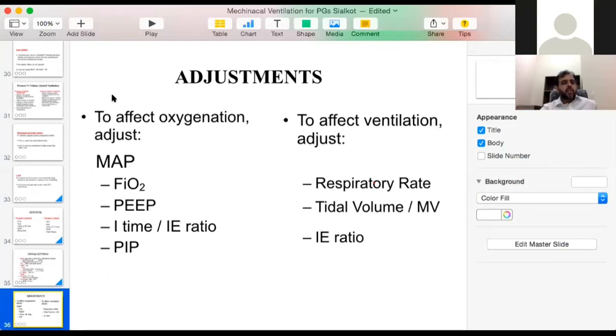If hypoxia is a major problem, then you increase any of these settings in a very fine-tuned manner. If there is a problem with CO2 retention, then you have to increase the respiratory rate, you have to increase tidal volume or respiratory rate, both, or you have to adjust the IE ratio. You reduce inspiratory time, increase the expiratory time. So these are the values to control carbon dioxide. These are the values to adjust oxygen.